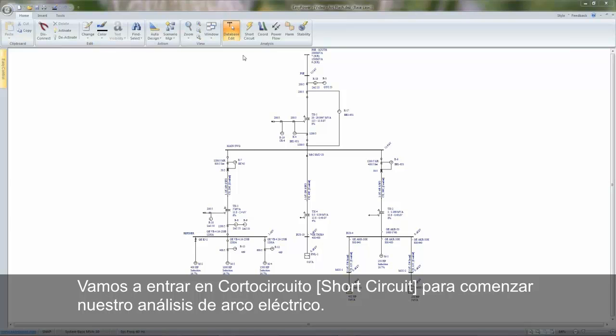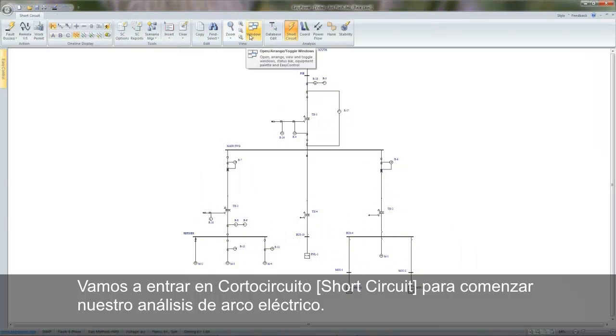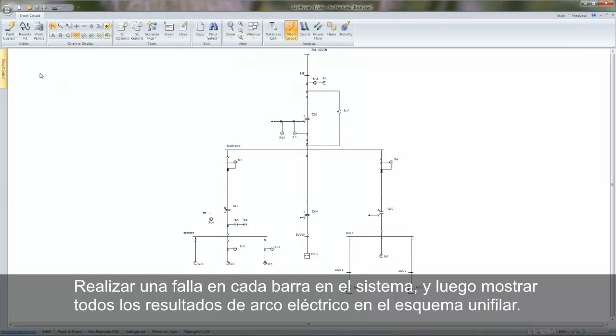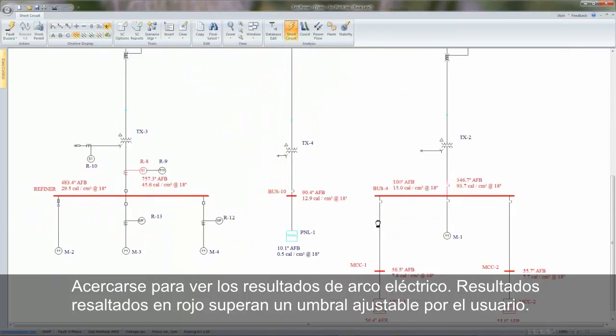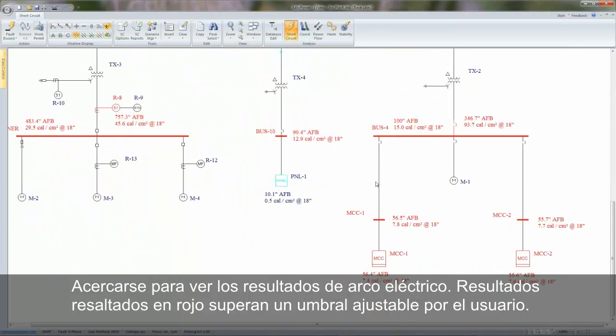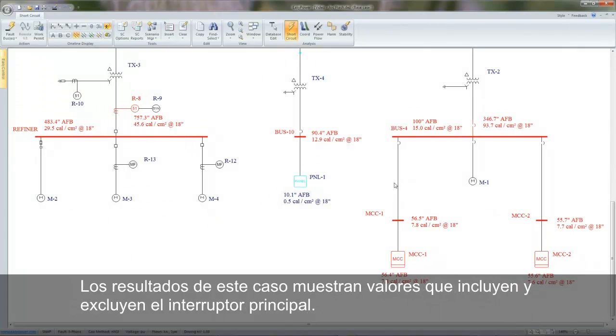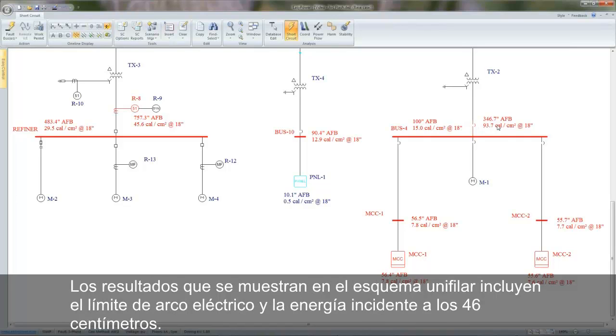We're going to enter short circuit to begin our arc flash analysis. Perform a fault on every bus in the system, and then show all arc flash results right on the one line. Zoom in to view the arc flash results. Results highlighted in red exceed a user settable threshold. Results for this case show values that include and exclude the main breaker. The results shown on the one line include the arc flash boundary and incident energy at 18 inches.